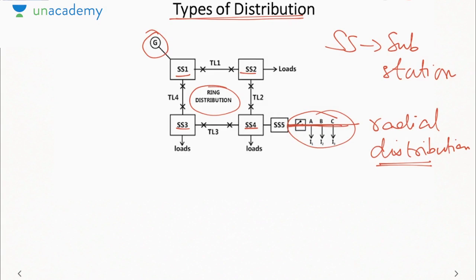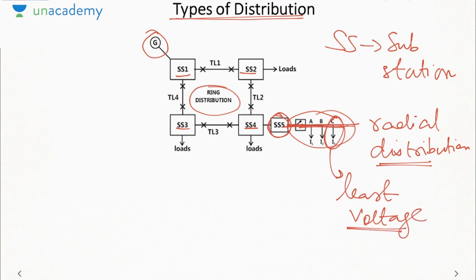In radial distribution, we are essentially supplying power from one substation to all the loads. So what are the disadvantages? First, the load at C will have the least voltage. As we keep increasing the distance from the source, the voltage will go on reducing, and at some point it will go out of the tolerance limit, because in India the tolerance limit is plus minus 5%. So as you increase the distance, it will violate that tolerance limit.